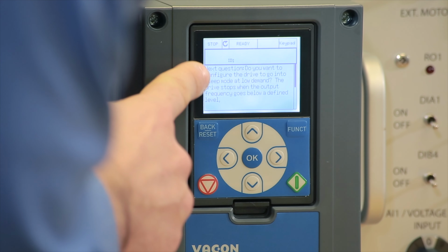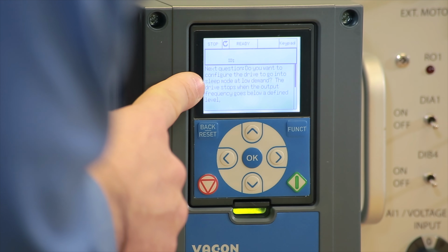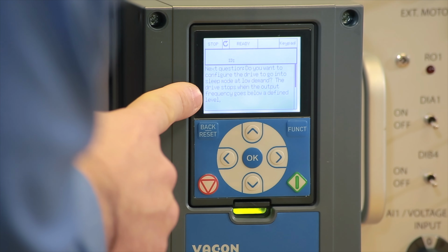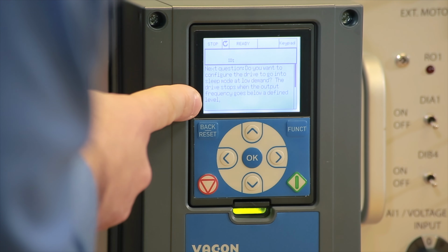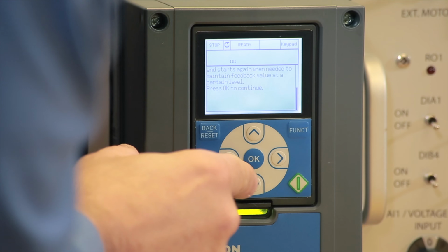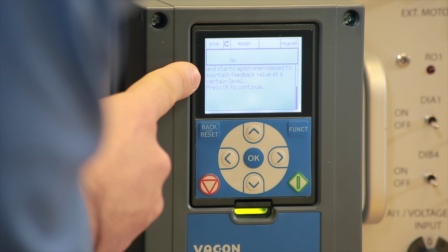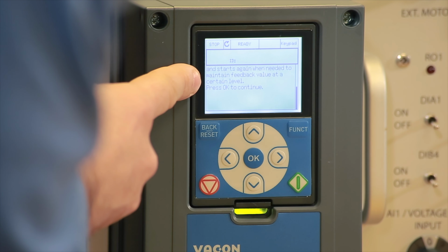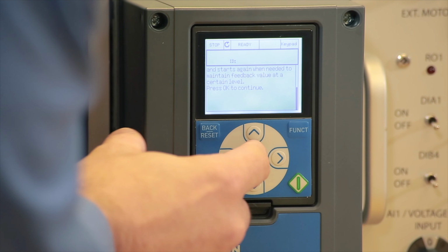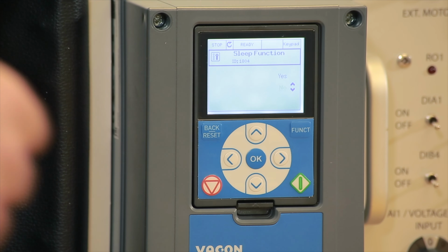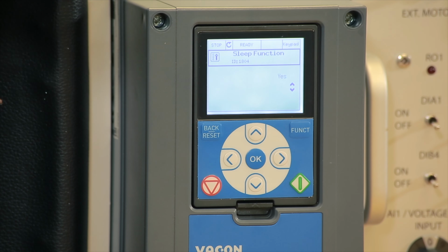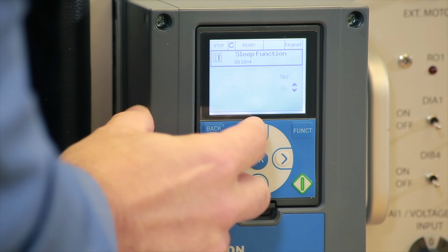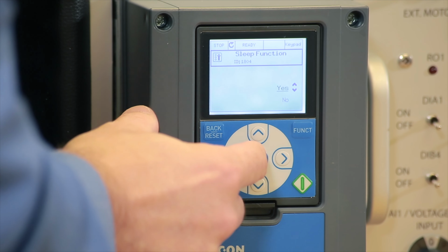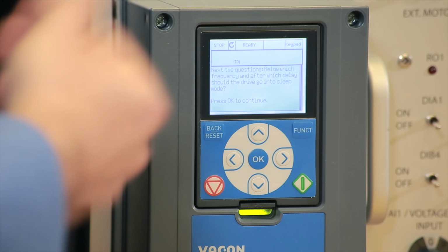Do you want to configure the drive to go into sleep mode at low demand? The drive stops when the output frequency goes below a defined level and starts again when needed to maintain the feedback value at a certain level. Press OK to continue. So, when the drive is not needed, we want to put it to sleep. This is the logical thing to do. So we will click yes. So up once, we'll click yes. We want to configure the sleep wizard.